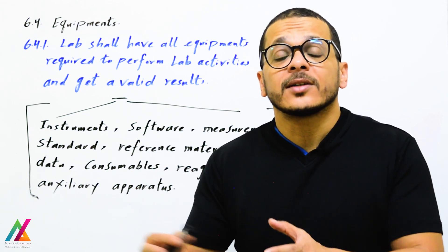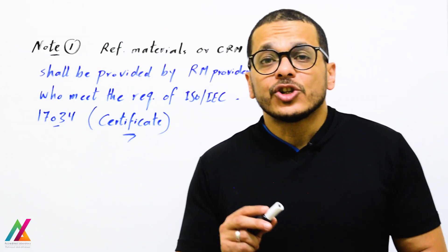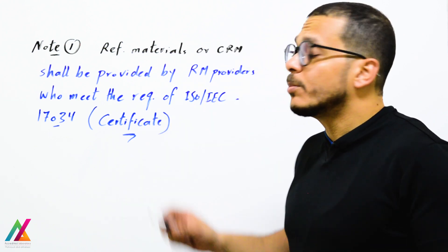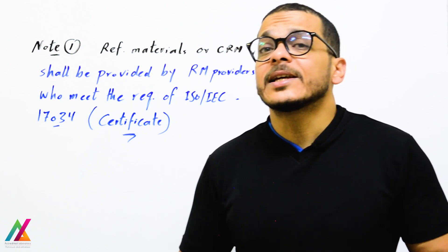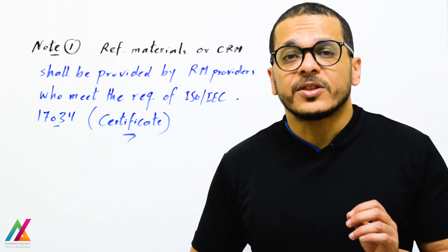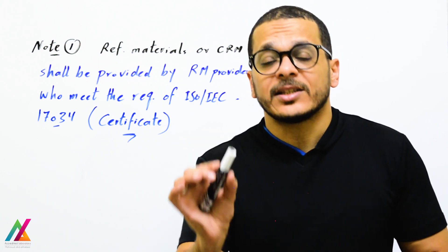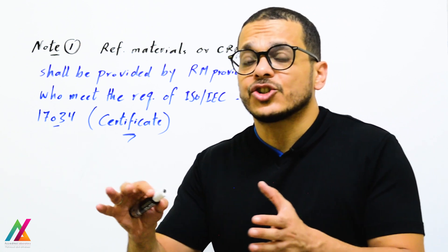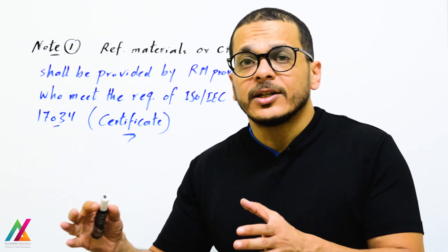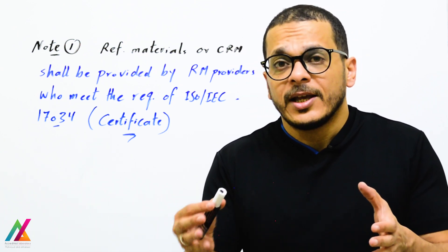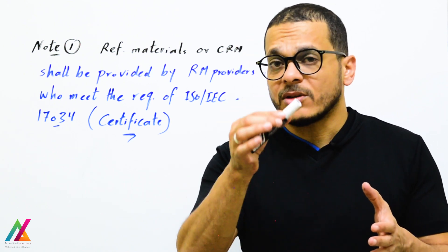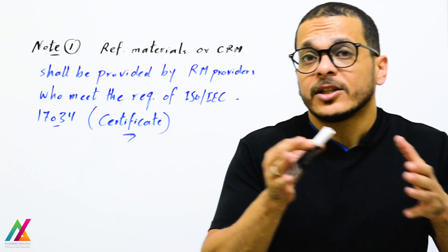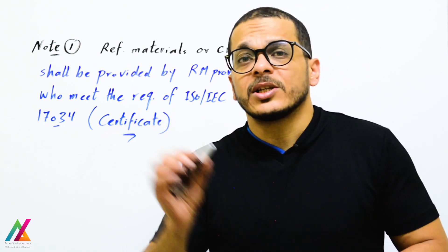All facilities related to the lab activity and the analysis of target analytes are now considered equipment. Note 1 states that reference materials or certified reference materials (CRM) shall be provided by a reference material provider who meets the requirements of ISO IEC 17034. The CRM certificate shall include homogeneity, stability, measurement uncertainty for each parameter, and metrological traceability, along with the target analyte results with an acceptable range.